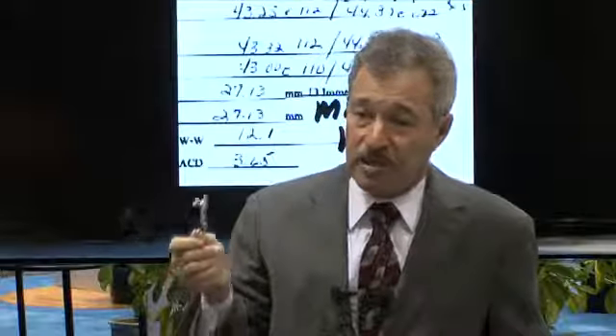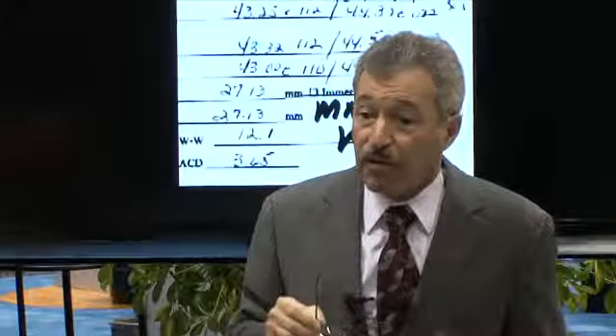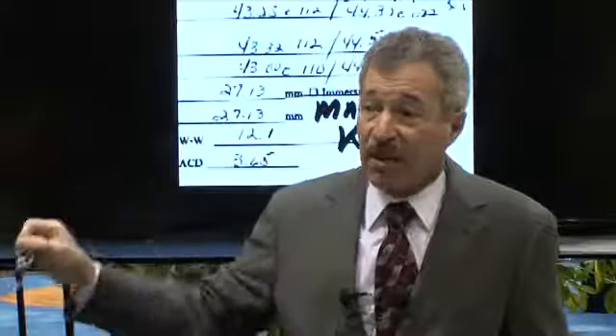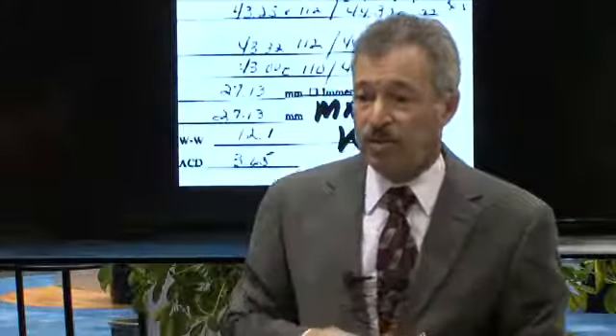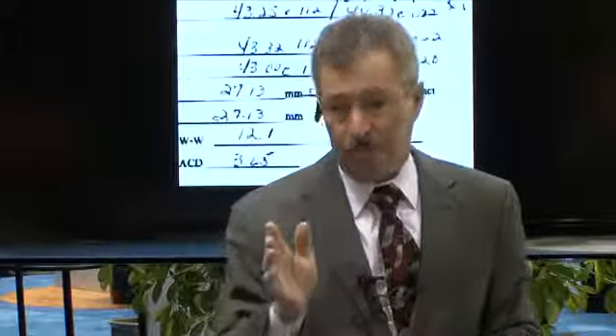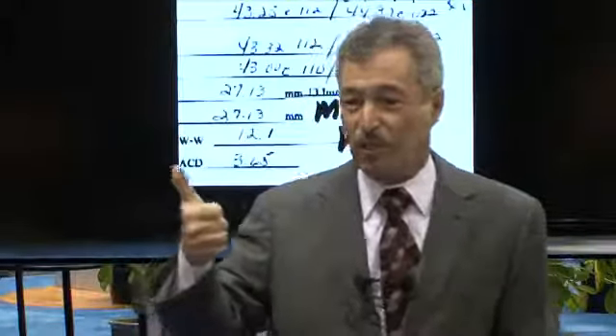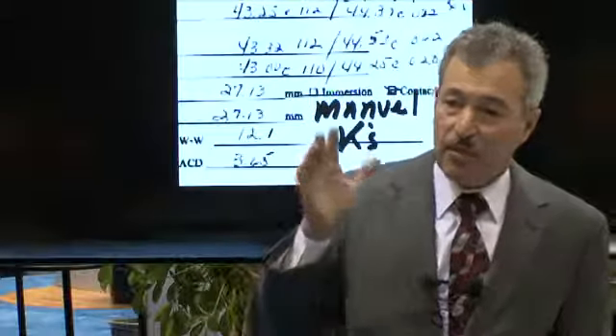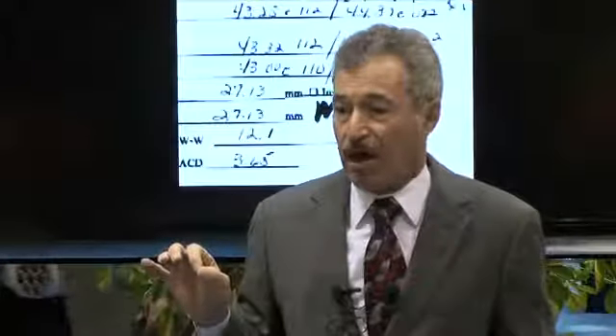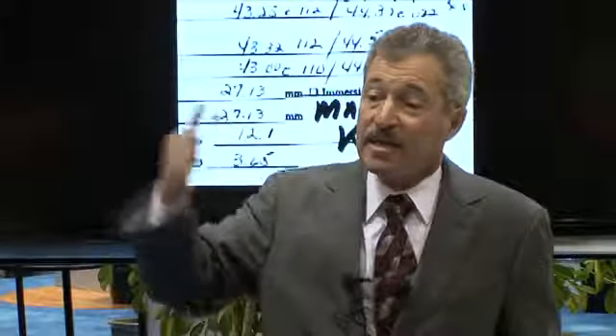I'm extremely honest and a bit of a loose cannon, so whatever booth I'm in they're always nervous about what I'm going to say. Every one of these technologies has outliers that can get you into trouble. The averages are terrific. I'll put Lenstar up against Manual K by the best people in the country, up against IOL Master, and up against topography. It won't show irregular versus regular astigmatism, which is why you still need topography — but if you look at averages, it's spot on. Don't just look at averages though: you need to look at averages and outliers.